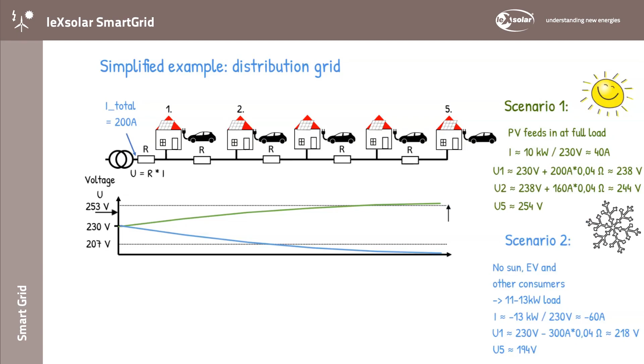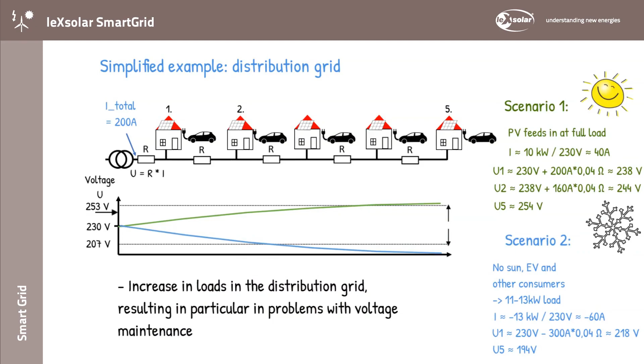problem. Whereas in the past there was no feed-in in the grid and thus the voltage at the transformer could be somewhat higher than 230 volts, the voltage band in the distribution grid is now being exploited in both directions and the outputs are increasing significantly in some cases due to electric cars, heat pumps and PV. Below we'll look at 3 different smart solutions for the simplified example.